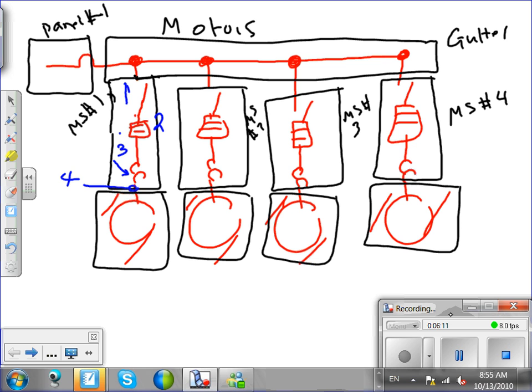Number three is the overload. The overload, guys, is a specially designed device for motors only, to trip in case of overloading a motor. For example, you have a pump that's designed to pump water 2 stories, and you go install this pump to pump the water 4 stories. So what do you do? You put a lot of load on that pump.